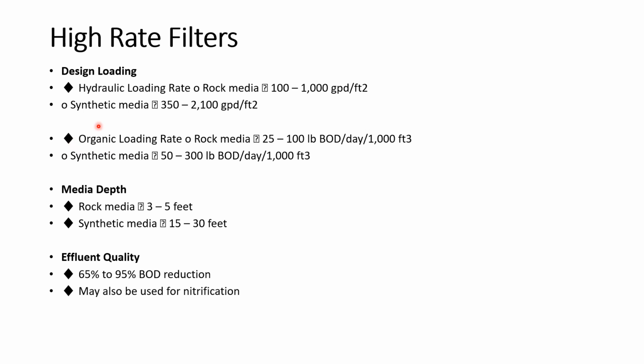And the organic loading for rock media is between 25 to 100 pounds of BOD per day per 1000 cubic feet. For the synthetic media, the organic loading rate is 50 to 300 pounds of BOD per day per 1000 cubic feet. And I told you both the media, that is rock and synthetic media, are used.